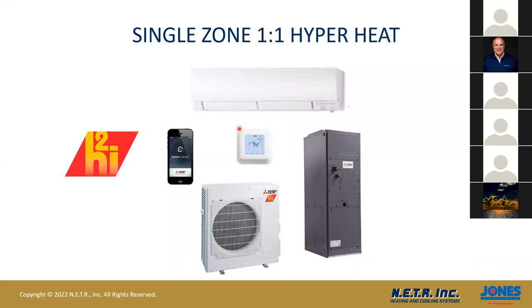Okay, there's the new thermostat I was just talking about. It's basically like a T10 Honeywell thermostat. Anything you're going to see in the Mitsubishi models that heat at low temperatures are always going to have this red logo on it that says H2i. That designates hyperheat. That's going to tell you that it is going to heat at a low temperature. Can be used in a wall mount unit or a ducted unit. Comes in many different varieties. There are different indoor units you can use as well with this. They're just not on the slide. Can also be operated by the Kumo cloud system that I'll get into in a minute.